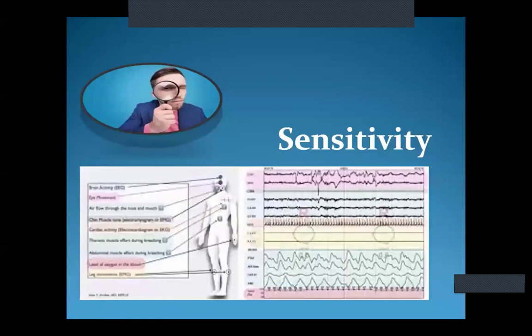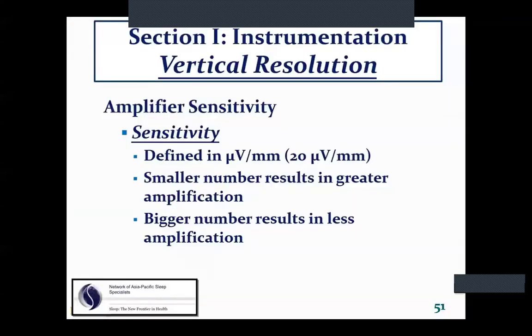Now let's talk about sensitivity. So the amplifier sensitivity is defined in microvolts per millimeter. For instance, an example would be 20 microvolts per millimeter. A smaller number results in greater amplification. A bigger number results in less amplification. So that's kind of counterintuitive. If my data is too flat, I need to turn it up. And when I say turn it up, I mean we use a smaller number. So if we started at 20 microvolts per millimeter and we have flat data, I'm going to turn it up then to 10. Does that make sense?